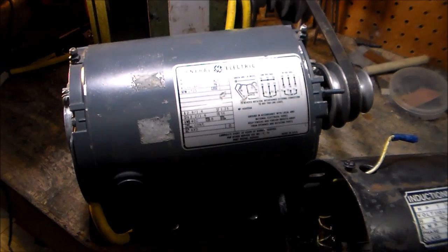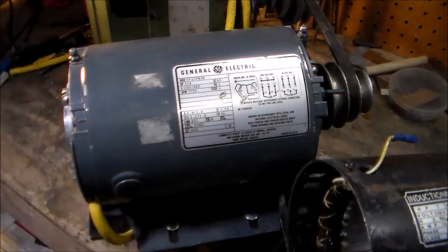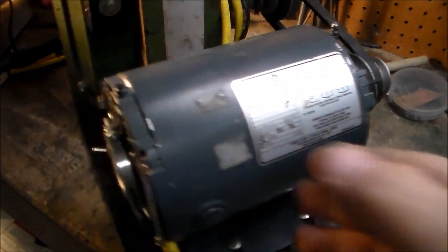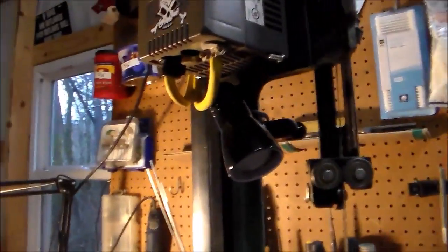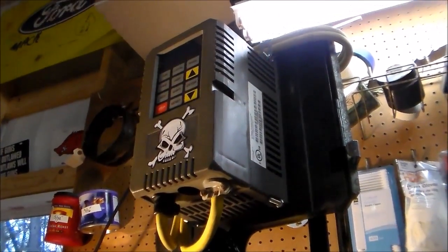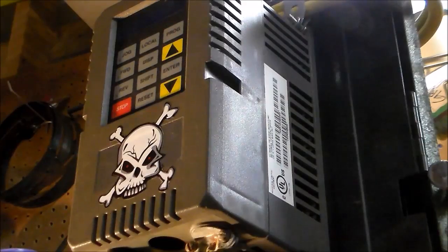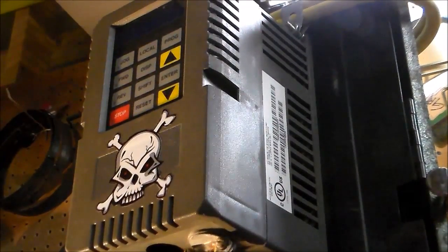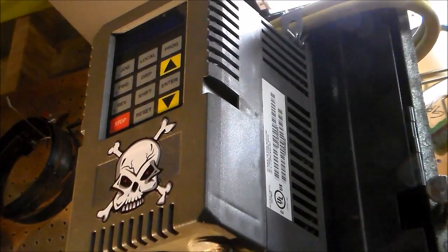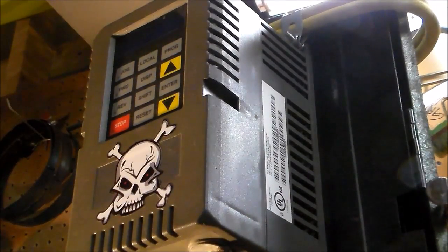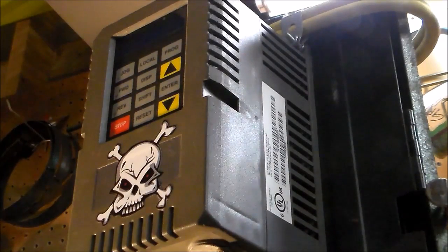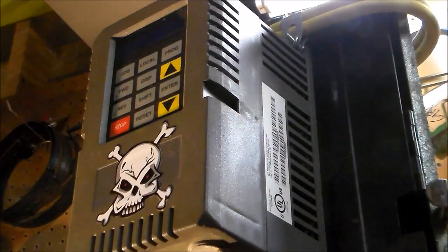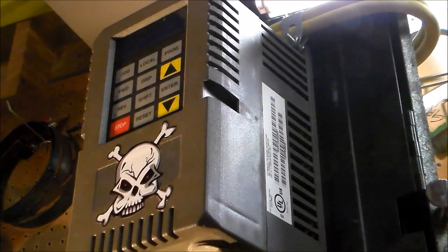The other part of the conversion, if you're wanting to go variable speed, is a variable speed drive or variable frequency drive. And they're not mysterious. They're actually fairly simple. The way these things work, they'll take single phase power in and internally there's a bridge in there. It converts it into a DC voltage, kind of a bus voltage. So it doesn't care whether it's three phase input or single phase input. Either one is converting it to DC. And then there's some switching transistors in there that chop that DC voltage back up into variable frequency.